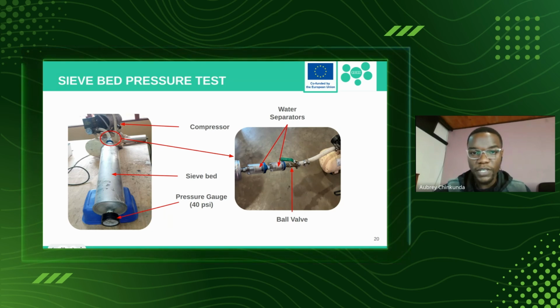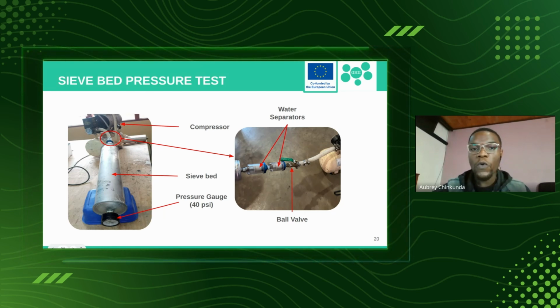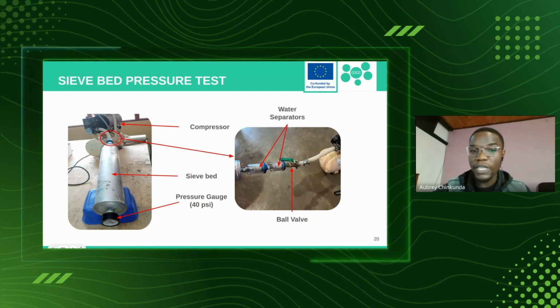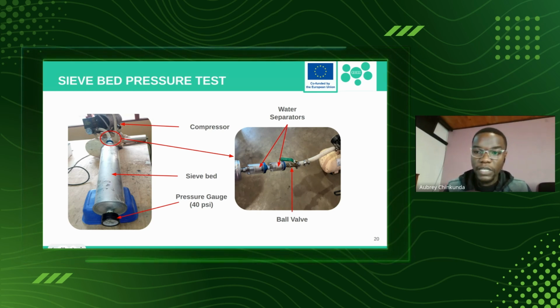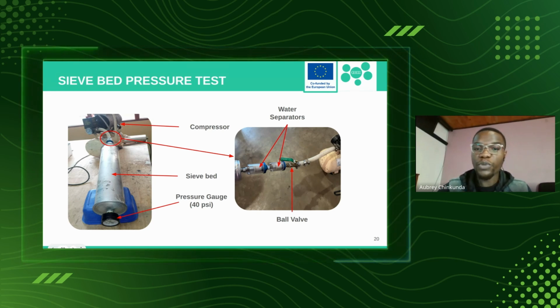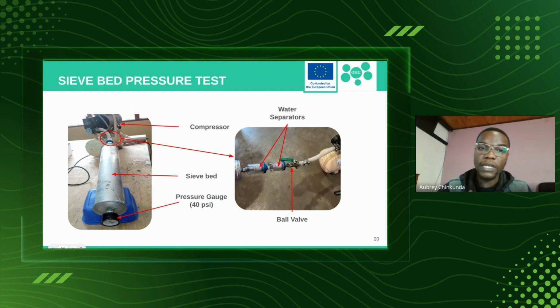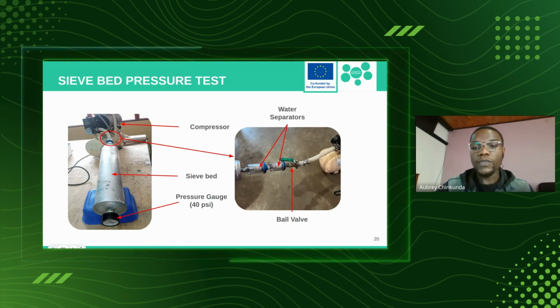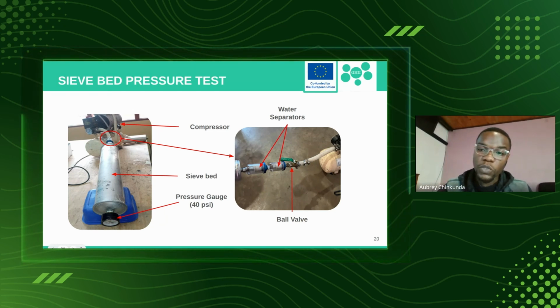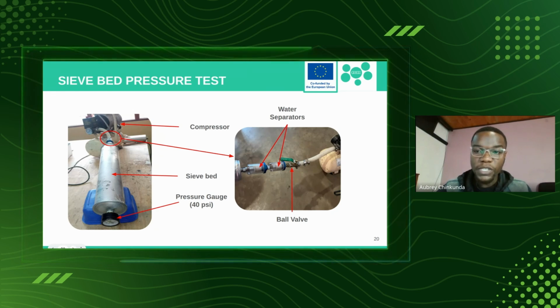2 water separators in series. This is just to make sure that we're not introducing any moisture into the sievebed, since now we have refilled the sievebed and we do not want to damage that zeolite inside the sievebed. Yes, it's an oil-free compressor, just like the ones that are in oxygen concentrators. So what we do is we connect the compressor to the water separators, to the ball valve as well, to the sievebed, which has the pressure gauge at the end.